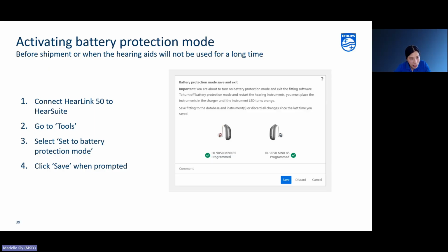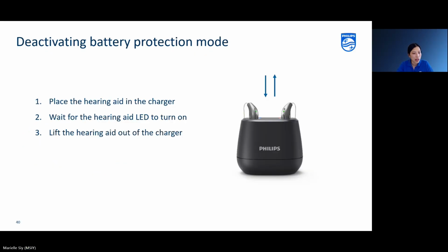And when it comes to activating this battery protection mode, it's pretty straightforward. You connect the hearing aid first to HearSuite, because no connected hearing aid means the battery protection mode will not be seen in the software. Then go to Tools, set to battery protection mode, and then click Save, and then your hearing aids are dead, basically. And if you want to wake up your hearing aid, you can easily do that by putting it in the charger, waiting for the LED light to turn on, and then taking it out of the charger. Then you can start using it.